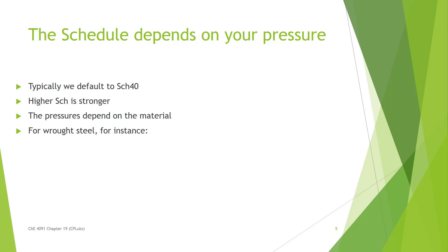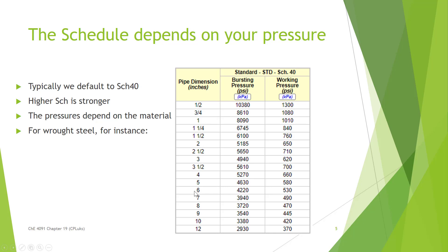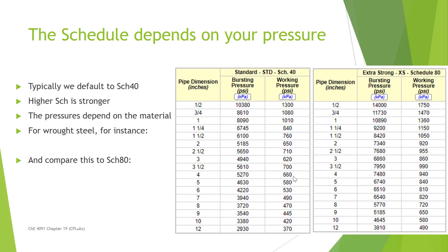For instance, on wrought steel four inch pipe, the bursting pressure is 5,270 psi and the working pressure — the one you should focus on for design — is 660 psi. Comparing this to schedule 80 at four inch, you can go up to a working pressure of 940 psi instead of 660 psi, which is a fairly significant increase. You always want to make sure you are selecting the schedule and diameter appropriate for the pressure you expect.